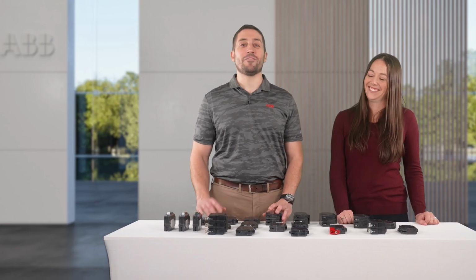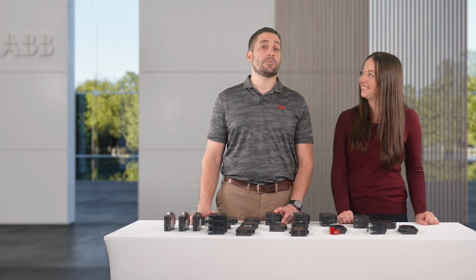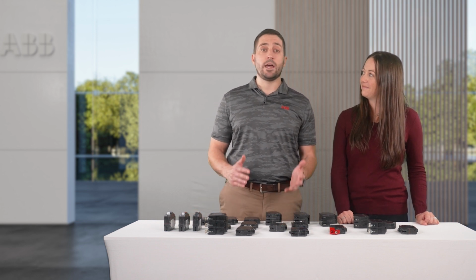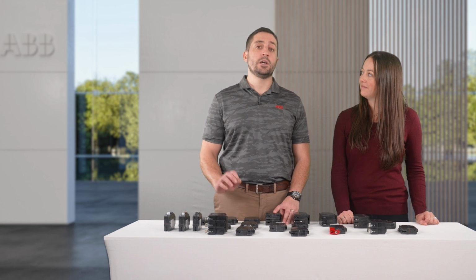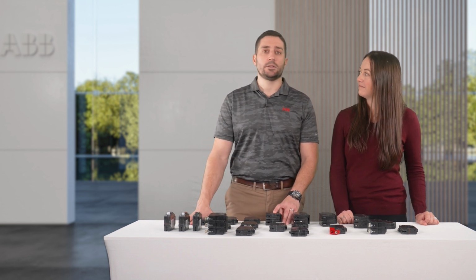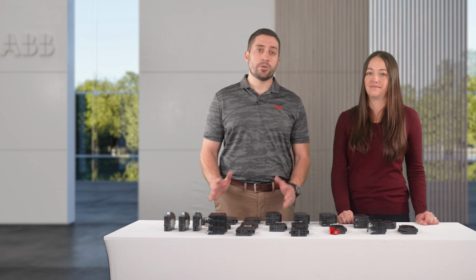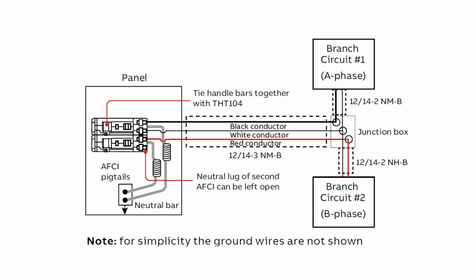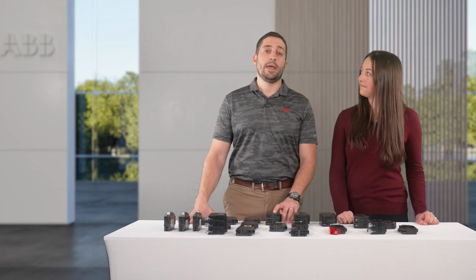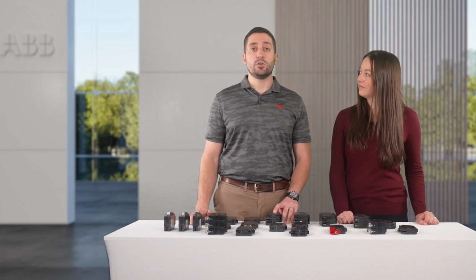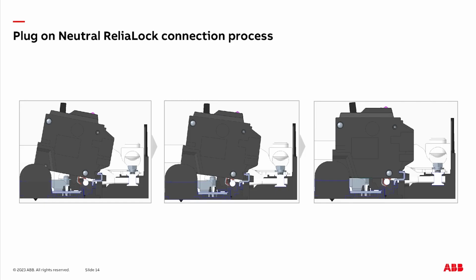Now you have a head start on retrofits because you don't need any pre-replacement research. You can treat your new AFCI Advantage breaker exactly like you would have treated the thermomagnetic breaker it's replacing. You leave the existing neutrals of the old thermomagnetic breaker terminated on the neutral bar as they were. You do not need to identify the neutrals and land them on a new arc fault circuit interrupter's neutral lug. Simply remove the old thermomagnetic breaker, replace it with a combination arc fault breaker by installing the hot wire into the breaker and either terminating the pigtail into the neutral or utilizing the clip connection to get the arc fault protection you need.